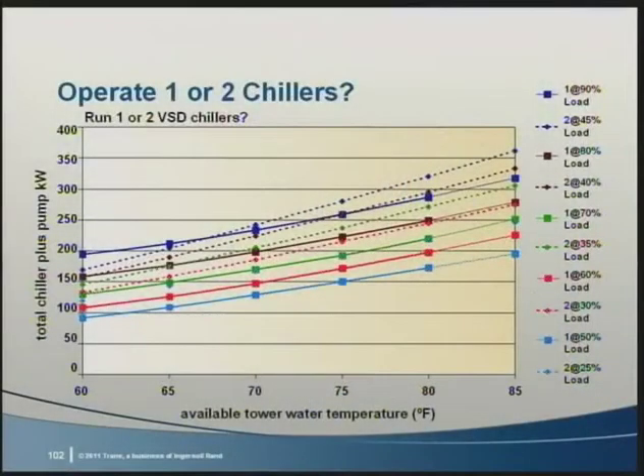But that's only one load point. Let's expand this and look at comparisons in different loads and different tower temperatures. This graphic compares 2 versus 1 chiller operation at building loads from 50% to 90%. Operating 2 chillers would put half that load on each chiller. The only time when operating more chillers is beneficial is when the tower temperature is below 65 degrees and the load on a single chiller is 90%. At all other conditions, operating fewer chillers is beneficial.